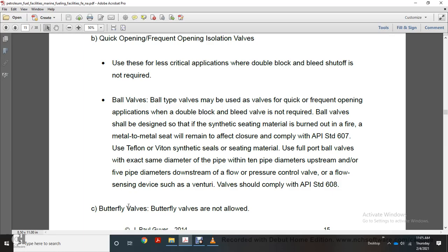Ball valves should be designed with a synthetic seating material, with a fire-safe design and a metal-to-metal seat that will remain effective with closure. Comply with the API standard 607 and use the Teflon or Viton synthetic seal seating material. Use full port ball valves of the exact same diameter as the pipe within 10 diameters upstream and/or 5 diameters downstream of a flow pressure control valve flow sensing device.